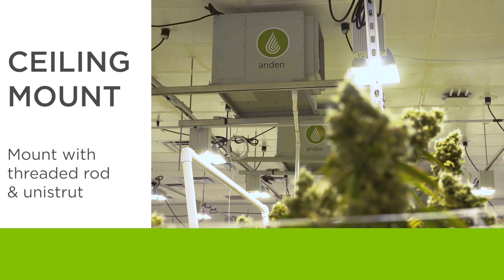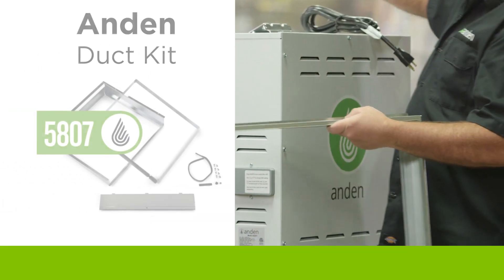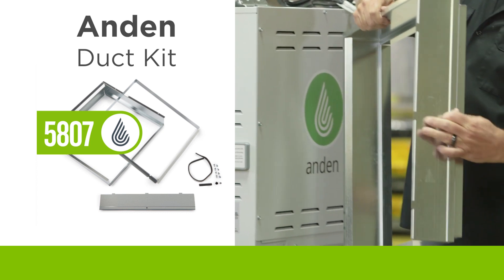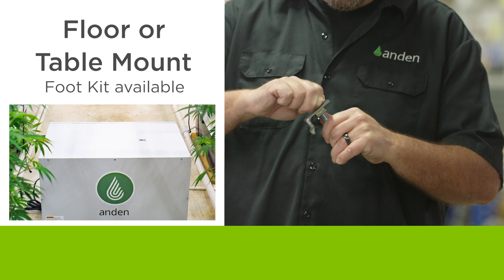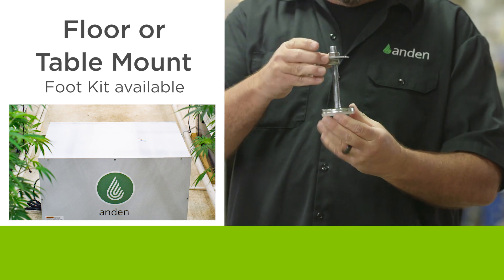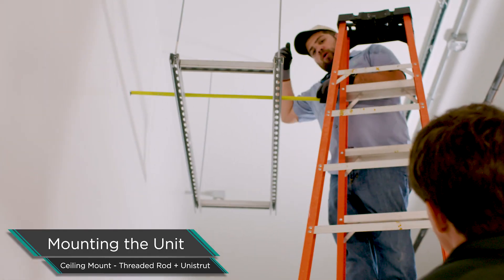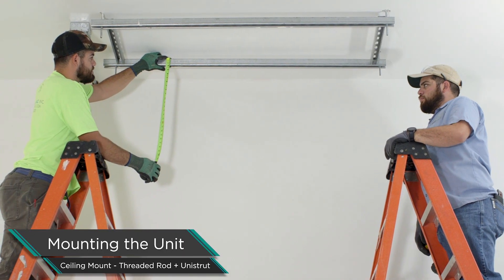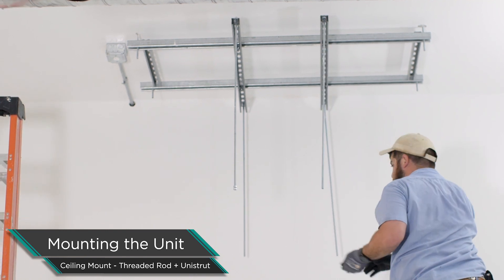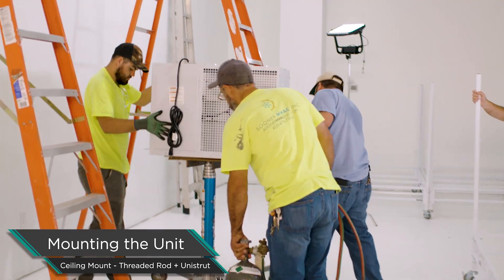Most commonly in the industry we see units being hung from the ceiling with unistrut and threaded rod. Today we're placing the unit inside the room and hanging it from the ceiling, but these units can also be placed outside the room and ducted in — just let us know and we'll walk you through best practice. They can also be set on the floor; the hanging brackets also accept our foot kit. We have the unit up and hung from threaded rod. In this application they had to work around items on the deck above the room, so they came down with threaded rod, added some unistrut, and made a little cage for the unit to hang from — perfectly fine, just a little more work.